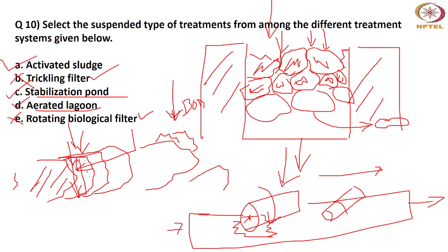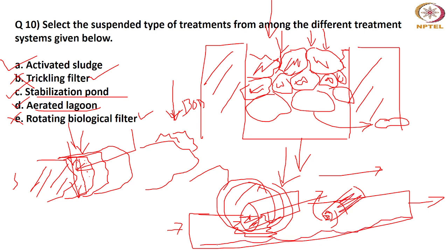So this portion of the drum was immersed in the wastewater, and after some time it is going up, right? This part will go up because this drum is rotating like that. So sometimes it will be down and sometimes it will be at the top, and again it will come down and this portion will go to the top. So they will continuously get oxygen, and due to this movement they will also slough off from the surface of this drum, and they will settle at the bottom of this tank. So we can remove them, and also we can get the supernatant liquid. I hope now this is clear.